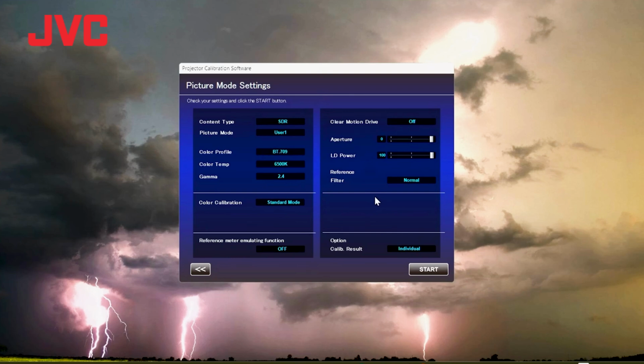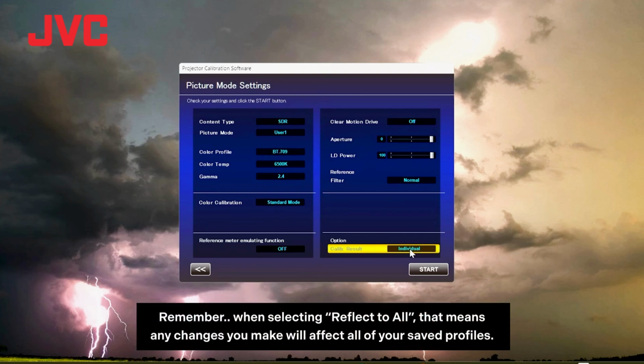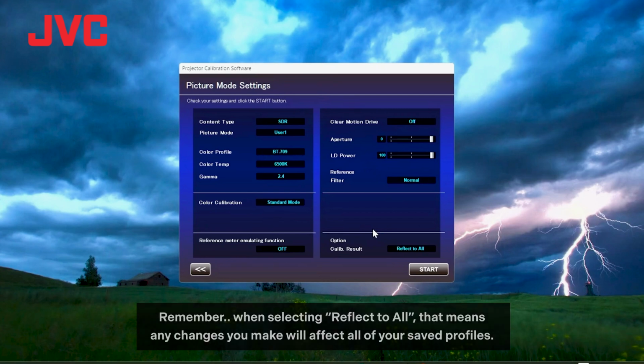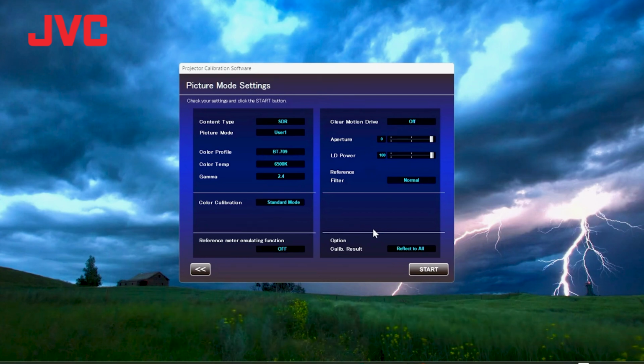And so what you're going to do is our reference meter should be off, which shows right there. If you double click on the option on calibration results, you can select individual, so this individual profile can be adjusted. Or if you double click, you can go to reflect all. Give it a second to load. Now it's reflect all. So that means we're going to calibrate the whole machine against all the different profiles. So now you'd want to turn off all the lights and start the calibration.